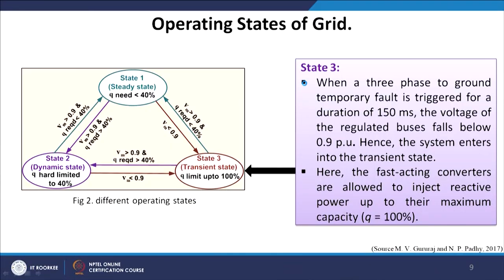The transient state is very important: when a three-phase to ground temporary fault is triggered for a duration of 150 milliseconds, the voltage of the regulated bus falls below 0.9 per unit and the system enters a transient state. Here the fast-acting converters are allowed to inject reactive power up to their maximum capacity — up to 100 percent.